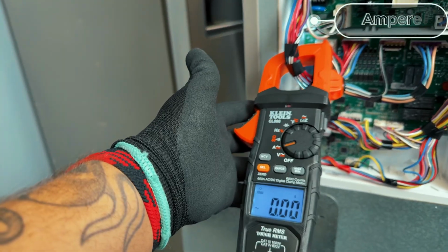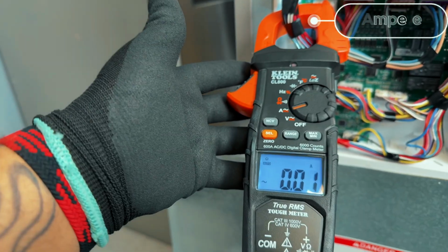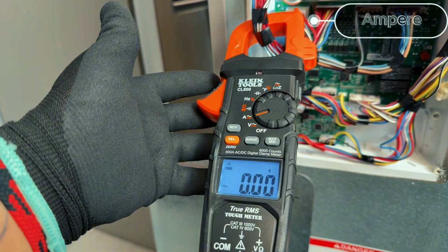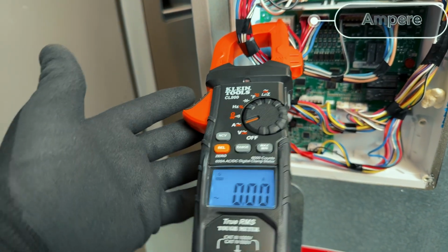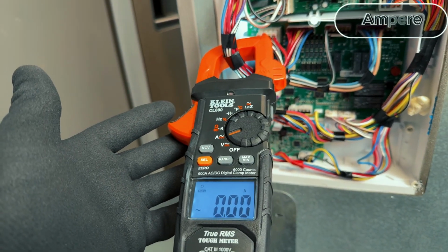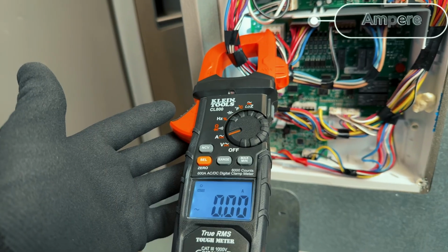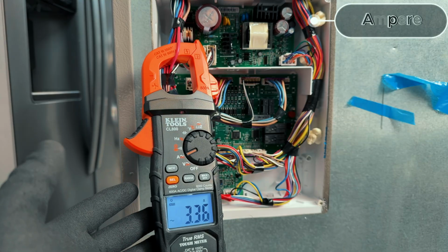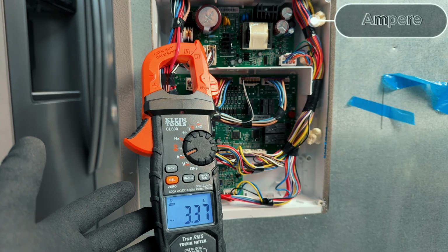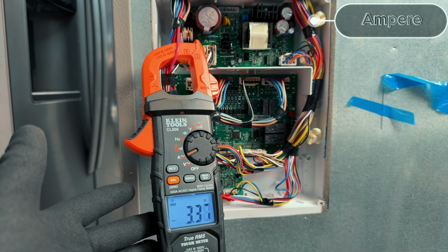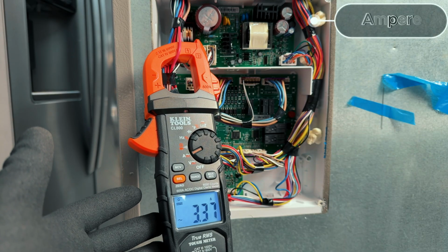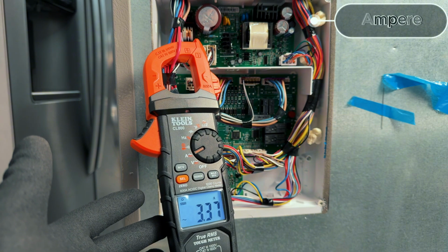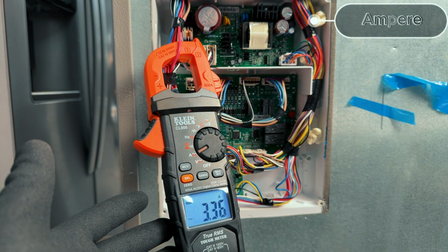You need to isolate just your circuit and make sure that you're isolating only the power wire, the main wire going to that load. And that's going to mean you're looking over your schematics and learning how to read it and understanding which wire you need to check your amp draw to. And situations like this will be really helpful where you don't have to take a freezer apart to check the operations of a defrost heater. You can turn the defrost heater on, and if you got correct amperage, that's going to tell you that the defrost heater is working and the defrost heater is okay. That's going to save me time on my diagnosis.